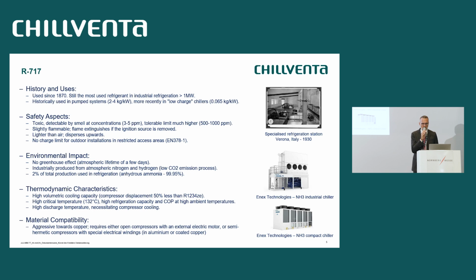Also, I'd like to point out the material compatibility issue. Ammonia is corrosive for copper. So for example, if you think about compressors, it requires an open compressor, where the electric motor, which has copper windings, is not in contact with ammonia, or a special semi-hermetic compressor with special electrical windings, for example in aluminum or in coated copper.